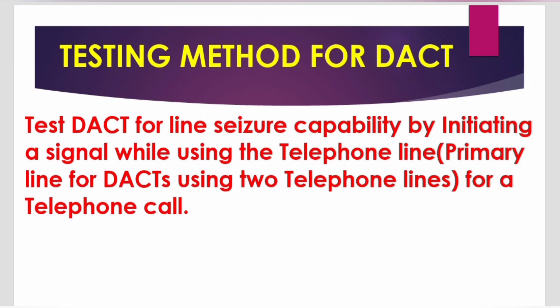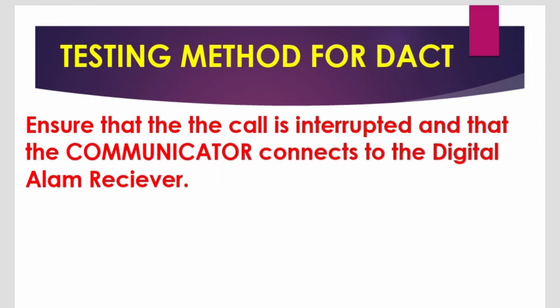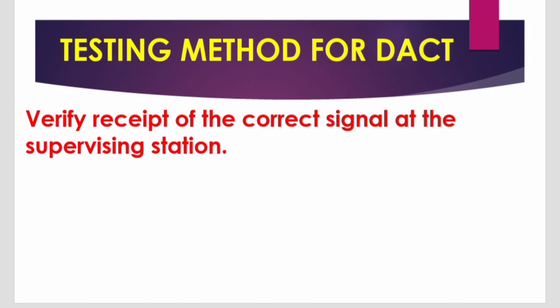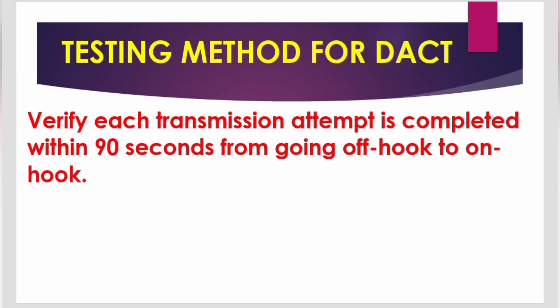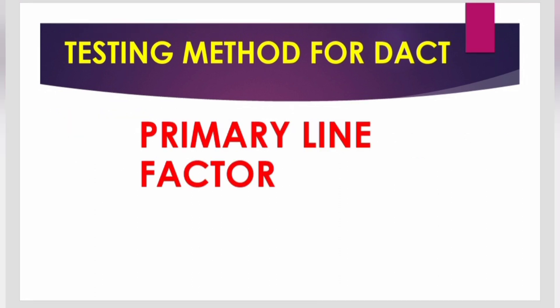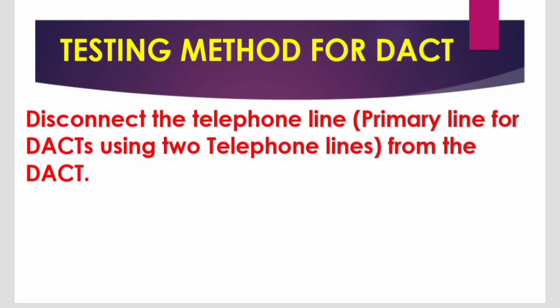While using the telephone line as the primary line for the DACT using two telephone lines, ensure that the call is interrupted and that the communicator connects to the digital alarm receiver (DACR), or verify receipt of the correct signal at the supervising station. Verify each transmission is completed within 90 seconds from going off hook to on hook.